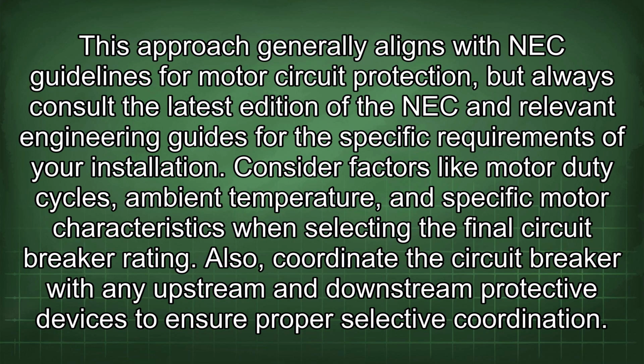Consider factors like motor duty cycles, ambient temperature, and specific motor characteristics when selecting the final circuit breaker rating. Also, coordinate the circuit breaker with any upstream and downstream protective devices to ensure proper selective coordination.